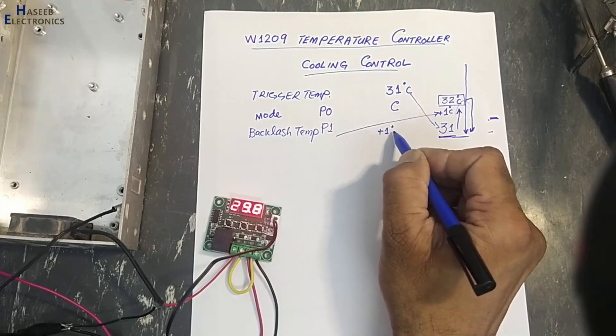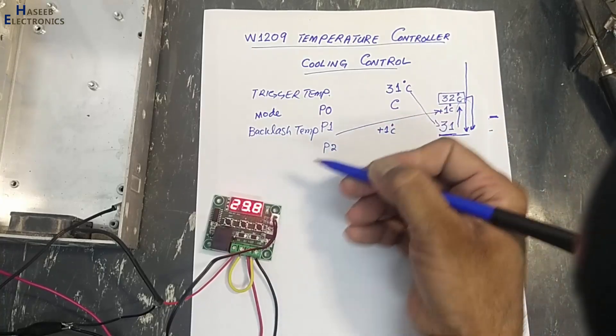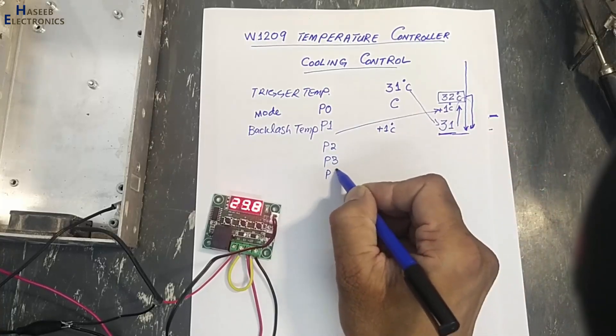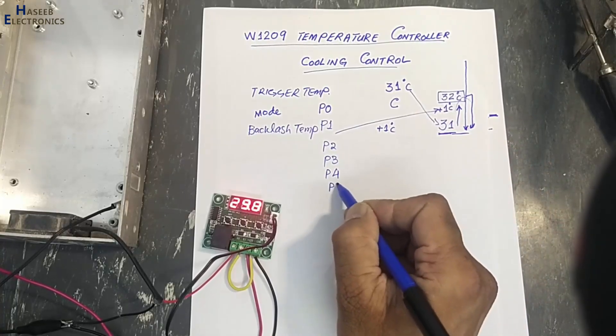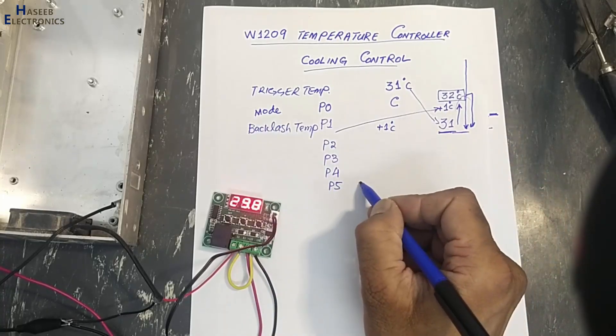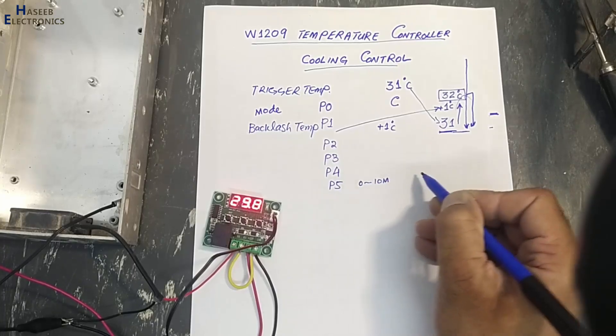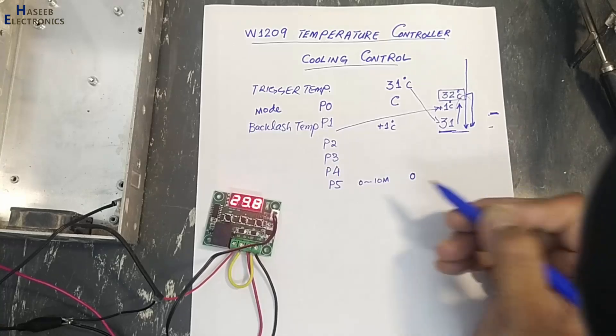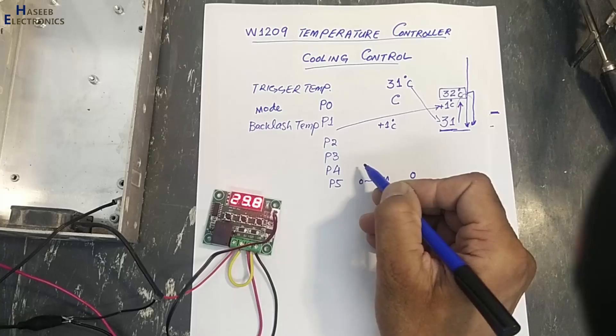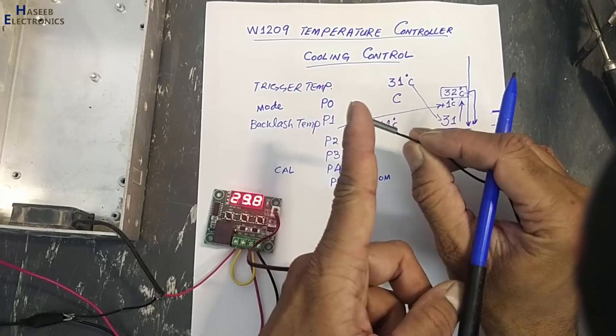P1 is set to plus 1 degree. P2 is the extreme upper level — we don't need to set it now. P3 is the lower level. P4 is calibration. P5 is delay start — if you want a delay, you can set 0 to 10 minutes, but normally we turn on the compressor or fan at the same time.